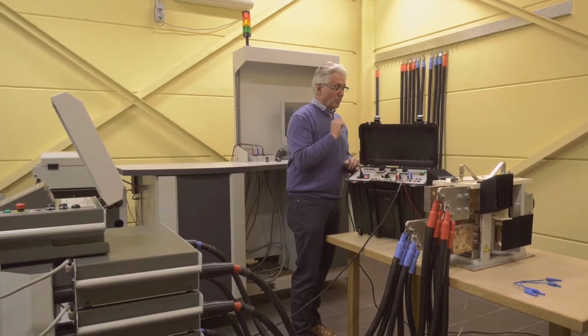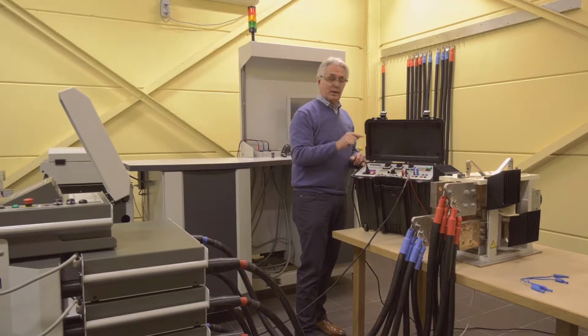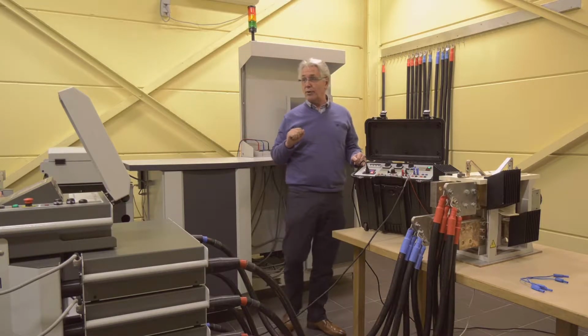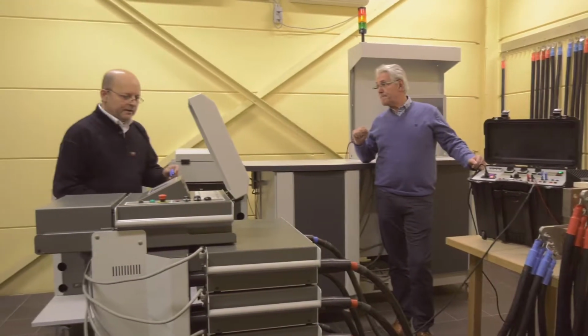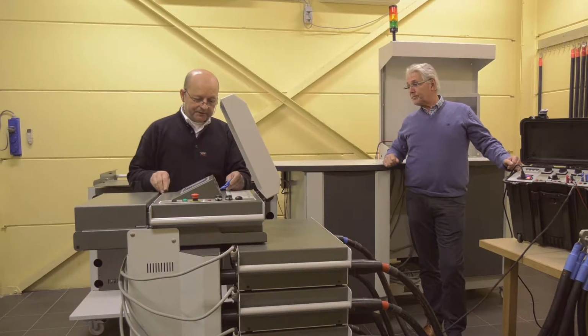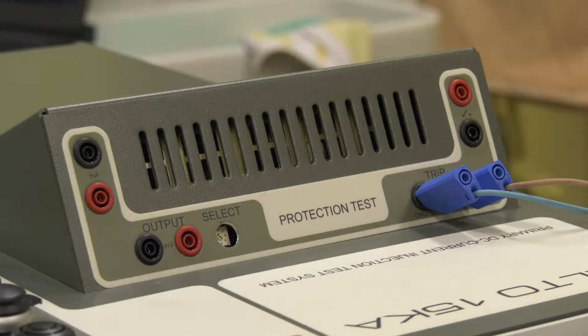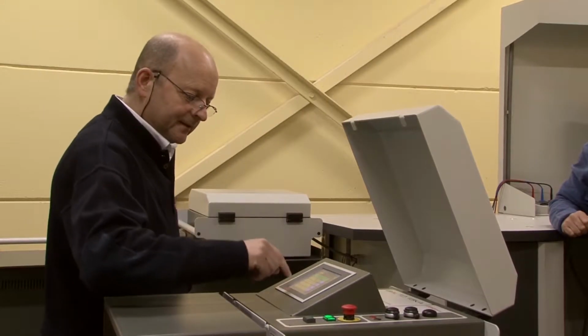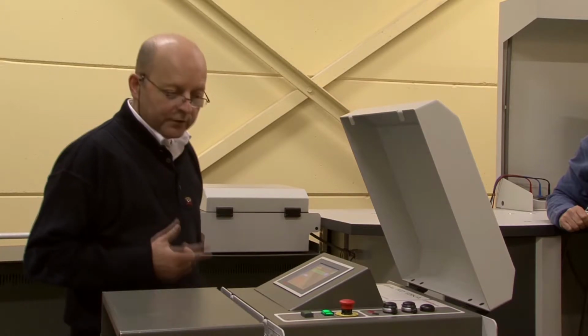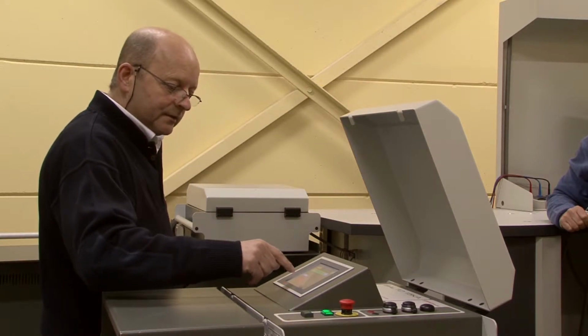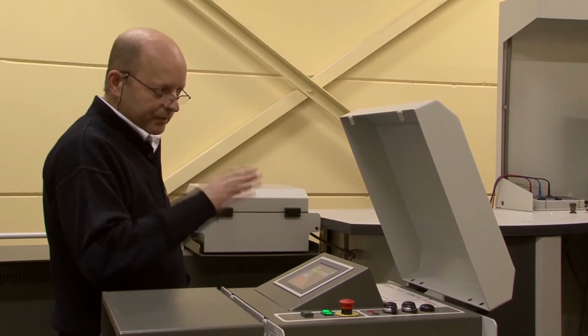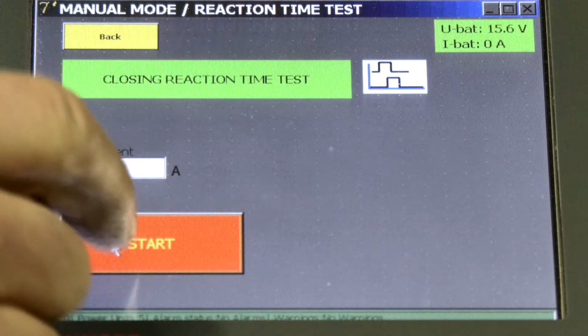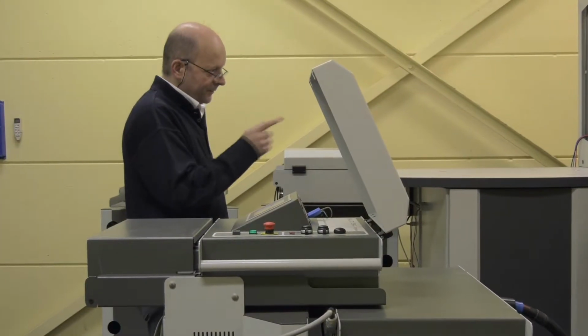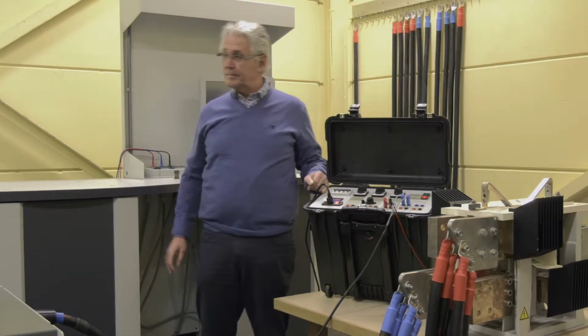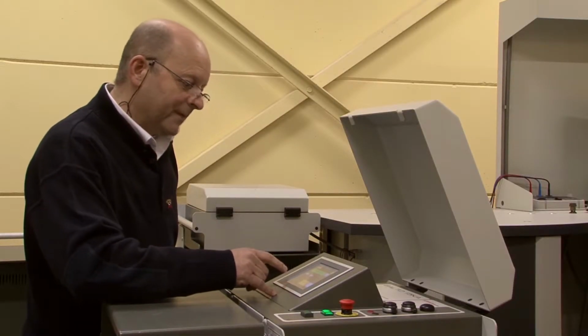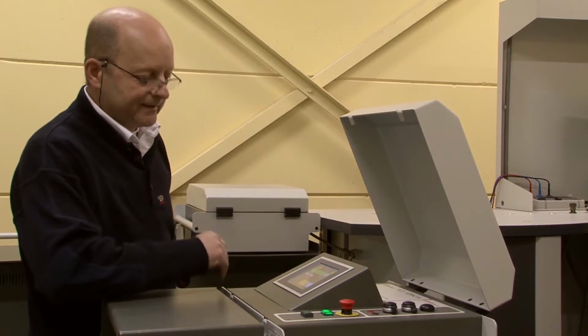And as soon as I push the close button, this dry contact will close and trigger the Balto controller. So the dry contact will be connected to the trip input of the controller. In the manual mode of the Balto, we can select the manual closing time function, and when I will start the function, then the Balto will try to push a current through the breaker. I start the function, now we can close the breaker, and the time measured for manual closing is 132 milliseconds.